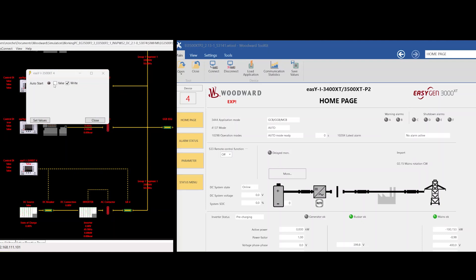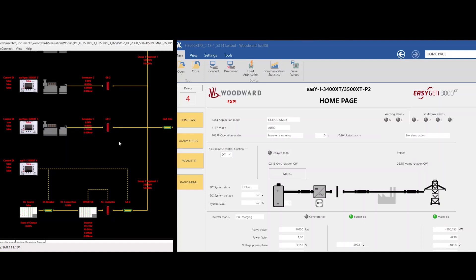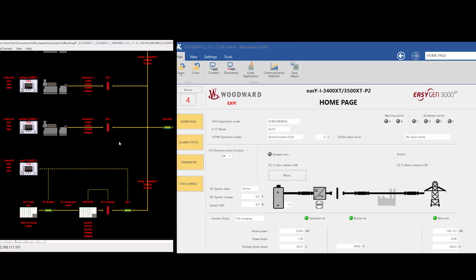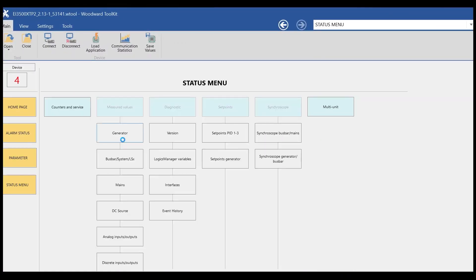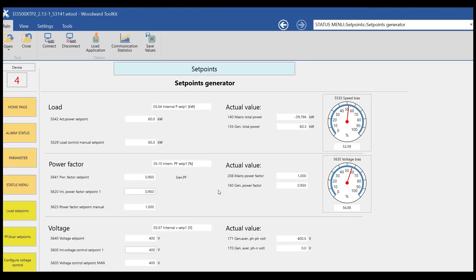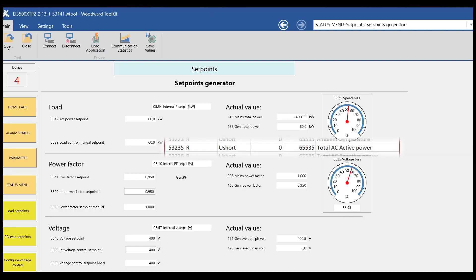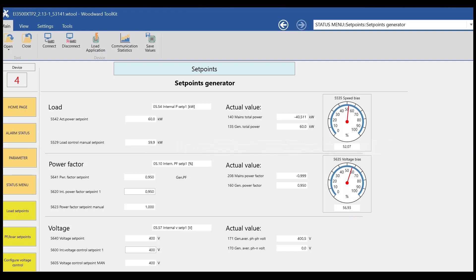When the EasyEye receives a start command, the inverter is activated and ramped up to the rated values. When the rated values are reached, the AC contactor is closed and the inverter is loaded to the active power setpoint of 60 kW. Let's check the setpoint screen to see if the desired power setpoint matches with the real value. This is shown as GEN total power in the setpoint screen — the corresponding value to analog manager input variable 55.04, where we map the active power value from inverter Modbus address 53235. As we can see, the inverter is running with stable values at the desired power setpoint of 60 kW.